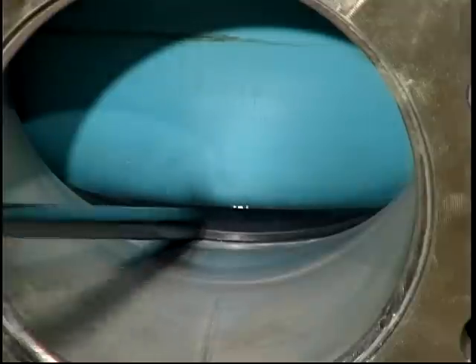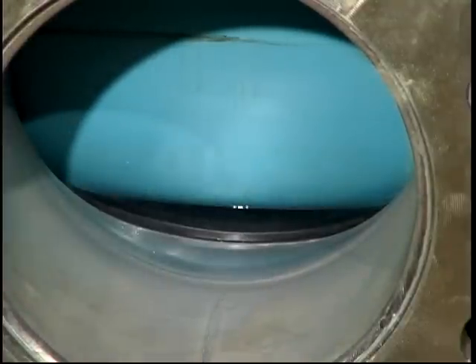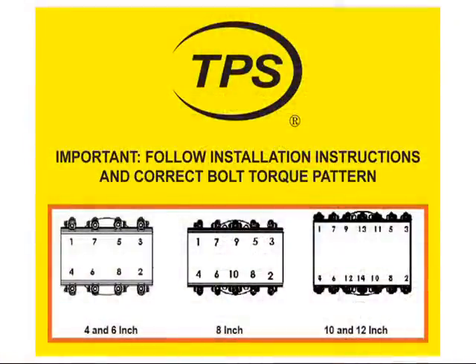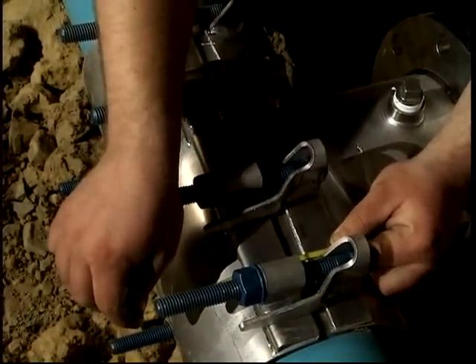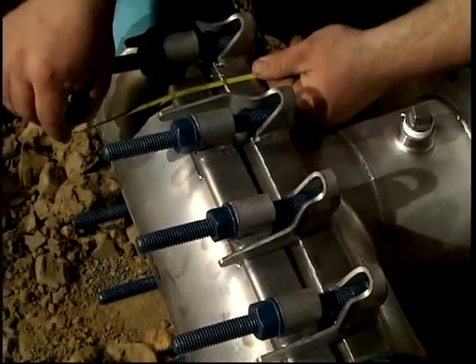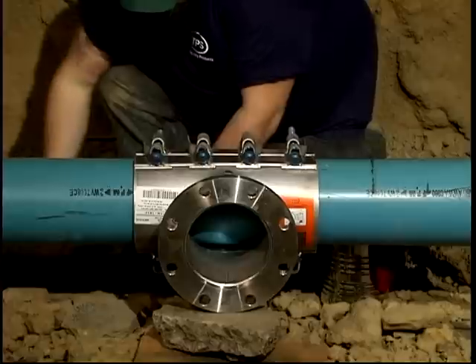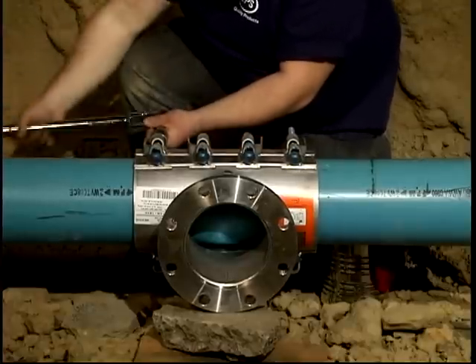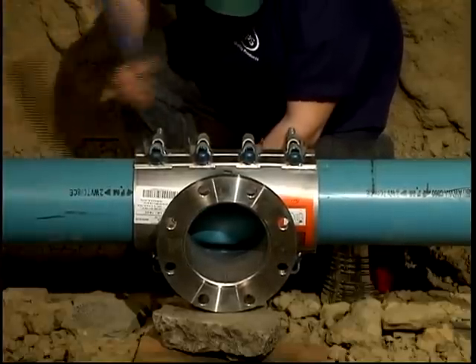Inspect the aperture seal to confirm proper seating between the sleeve and conductor pipe outer surface. Begin wrench tightening bolts in a staggered pattern as shown in the printed installation instructions. Make sure the spanner shell gaps are even on both sides of the sleeve, or the tapping sleeve will not seal properly. Tighten all bolts to approximately 50% of final torque, then repeat the tightening sequence to 100% of final torque value. Refer to the installation instructions for proper torque.